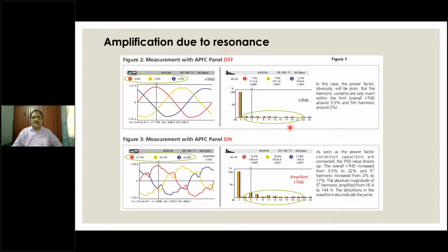Now I spoke about resonance. If you recollect that graph where the grid impedance and the capacitance resonate, they will create amplification of harmonic. As you can see here, this is the pure sine wave when the capacitor is switched off, when the APFC panel, the automatic power factor correction panel, is switched off. The same thing when it is switched on, you see the distortion. This is harmonic. From 3.4, 3.5, 3.8% in RYB, it is increasing to 21.5, 23.3 and 22.8. This is primarily because of the resonance that is taking place.